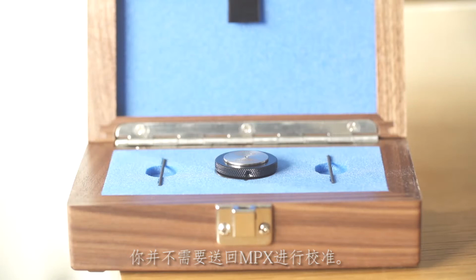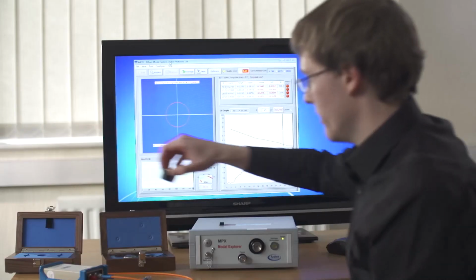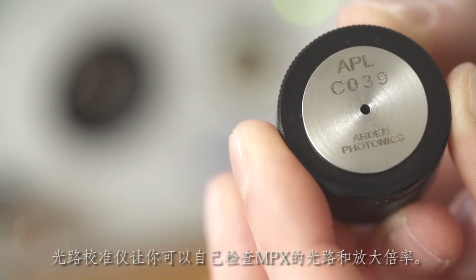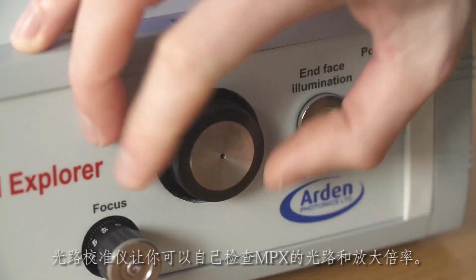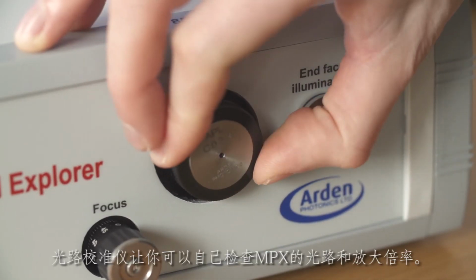And you don't need to send the MPX away to be calibrated. It can be provided with a geometric calibration artifact so that you can check the geometry and magnification of the device at your own premises.